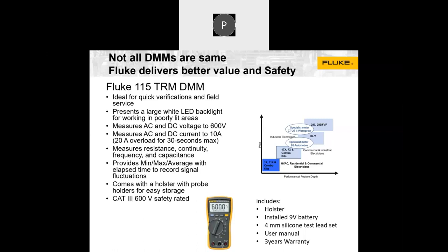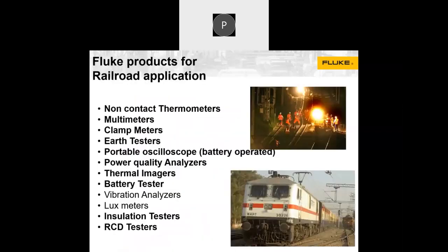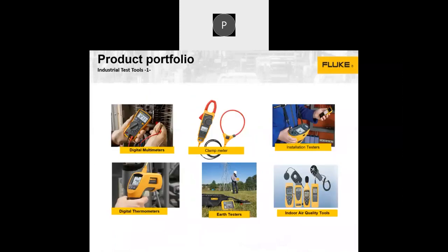This is the device - let me show it to you. This injects leakage current into the RCD or ELCB and gives you the timing of how fast it trips. It verifies whether it's tripping, and also tells you the loop impedance - how much the loop impedance is and how fast it trips at what current.